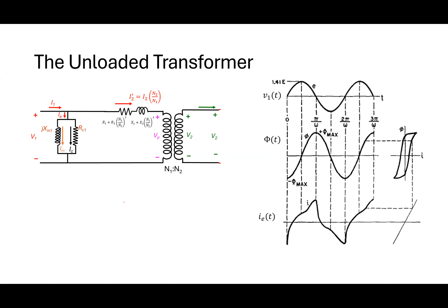Typically when the transformer is unloaded — meaning I put a voltage source on the primary with nothing on the secondary — I get a flux and a current. I keep calling this I-sub-e; the 'e' means exciting current. It's the current required to excite the transformer — to make the magnetic field happen inside. If the transformer were ideal there would be no current required, but because it's real I have to magnetize the core, and some current goes into that process.